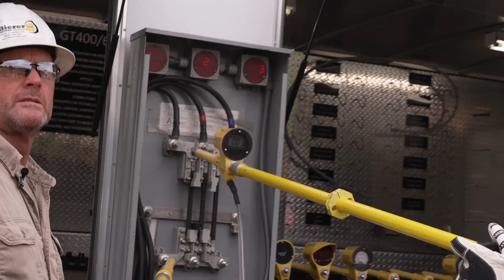Okay. Go to our secondary panel. You get that, Skylar? Good. So we get about 1 volt. So we see close to zero, in phase. We've got a little bleed on that cable. The grass is wet, so that's why you're showing 1 volt. So the cable has a little bleed on it. We go phase to ground, seeing right at 120 volts. Phase to phase, 210 volts.